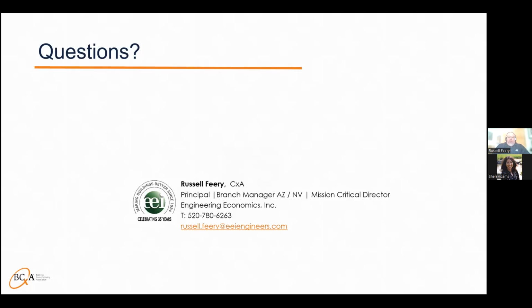Yeah, that's a great question. We found that there were some issues during startup with condensate sensors. Those were fixed and we didn't have any repeat or failures after they were. There are opportunities that you could use a room humidity and calculate dew point. Then you're kind of reliant on the network to pass that information along. So you're kind of shifting it from a sensor that's potentially local, that is your safety, to something that you're relying on a calculated value within the program and it transferred across the network to do your safety. So it could be done either way. Of course, I would lean towards having something that's a little more localized and a little more of a safety type, hardwired safety. But there are opportunities that you could do that under programming for sure.